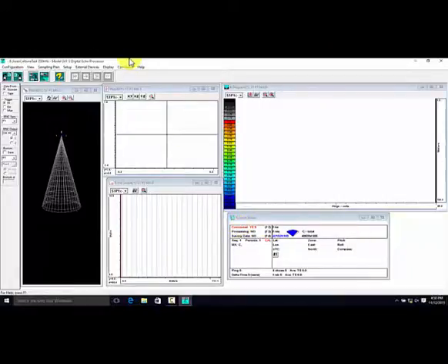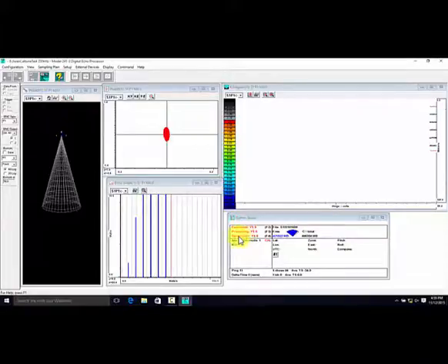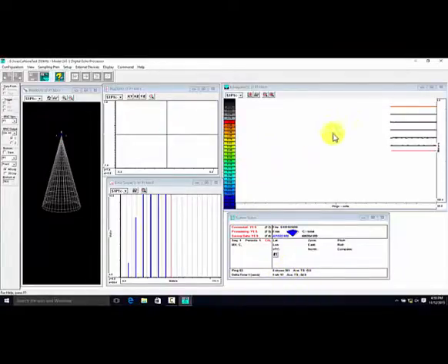Now that we are connected, we will go Command, Start Processing. This command can also be completed with this toggle button right here. Either way, we'll do the same thing. I will click the toggle button to begin processing. And as I do that, I see down here in System Status that saving data is now yes, processing is now yes. Our ping rate right here is ascending, and we are recording live statistics down here. In our echogram window, we begin to see our data coming horizontally across the screen. In our 2D plot, we see our data here, and in our echoscope, we see these vertical lines.